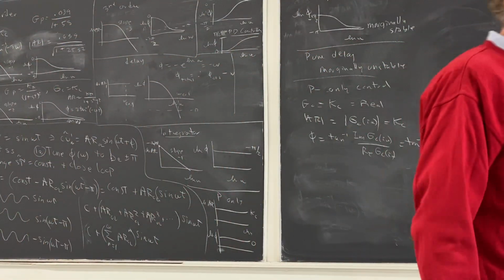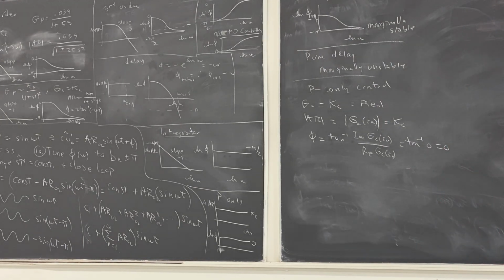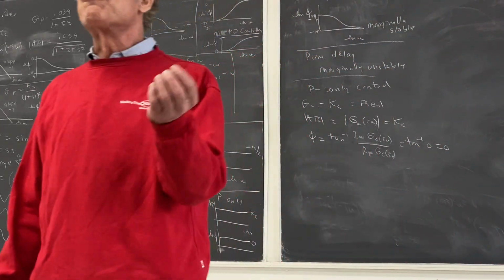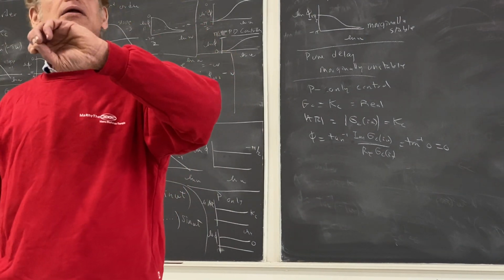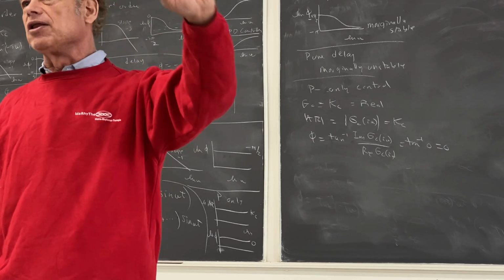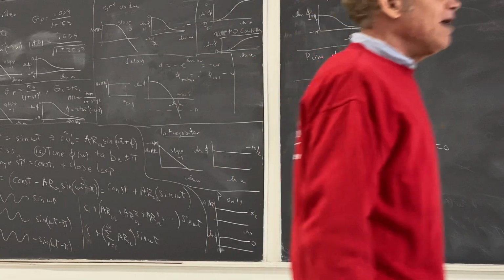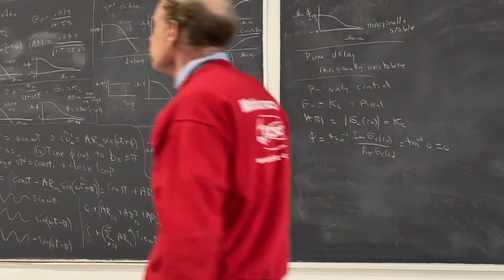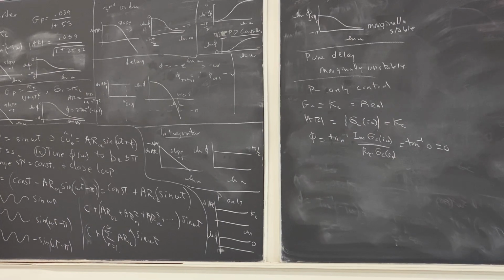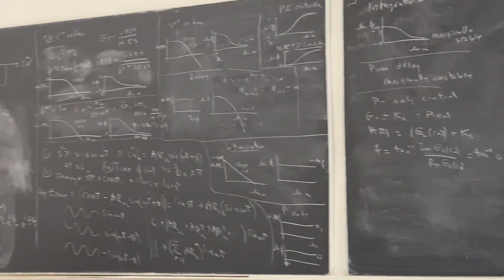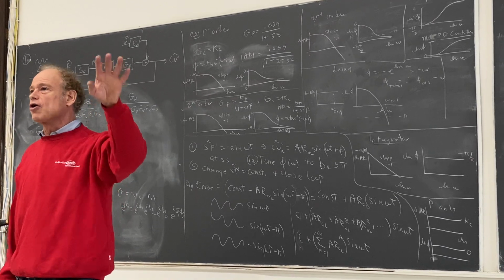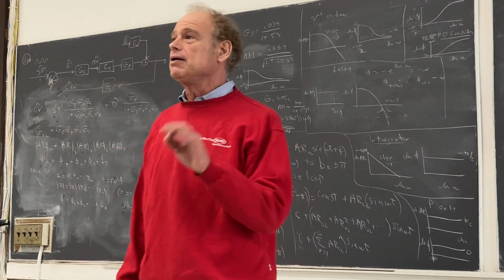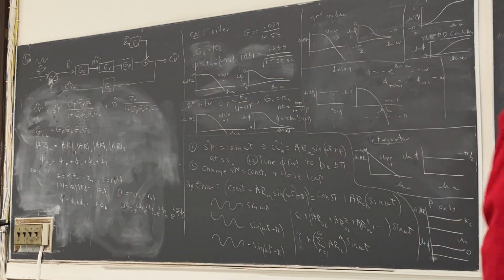So you want to find that compromise, and the methods we spoke about were sort of brute force as well as correlations relative to a particular model, where the particular model was a pure delay followed by a first order process. If your true GP can be approximated well by a pure delay followed by a first order process, do it, use those correlations. But if that is a pretty crappy approximation, then that's not a good way to go, it depends on your system.